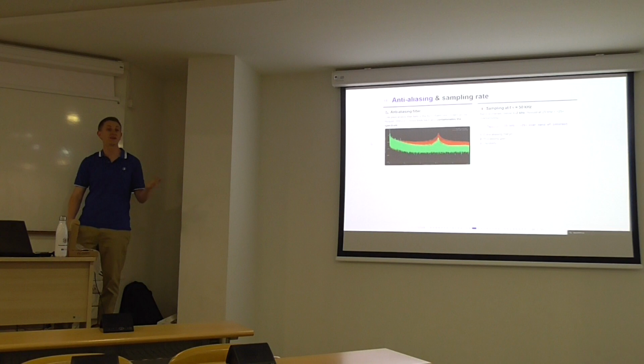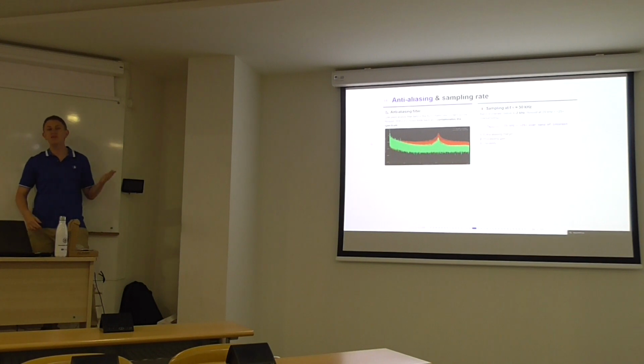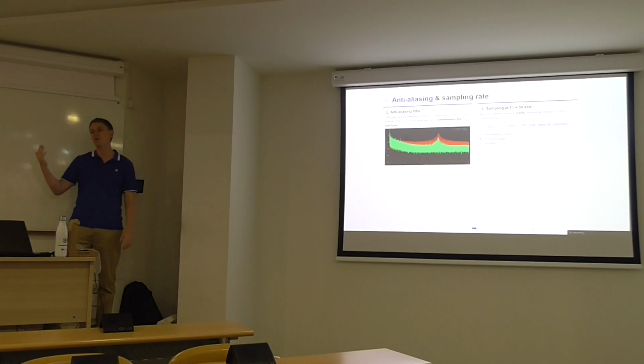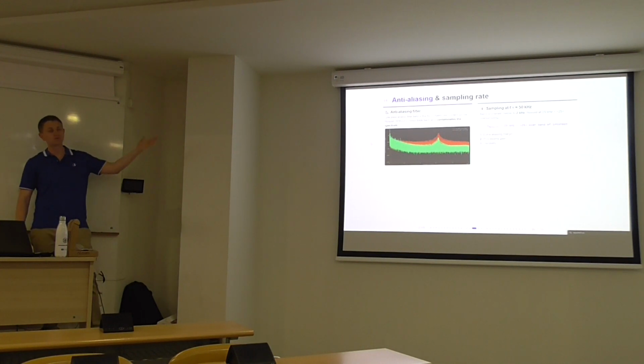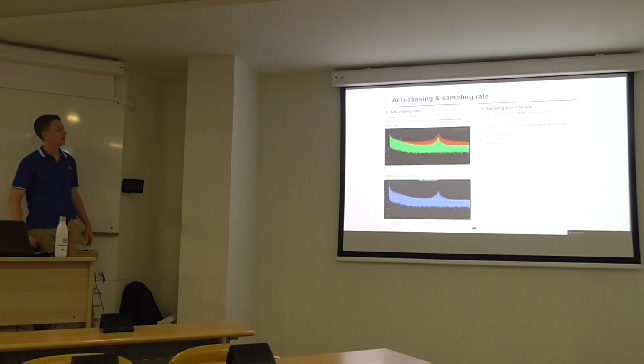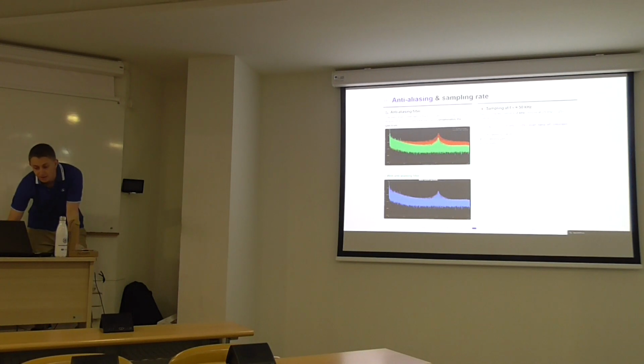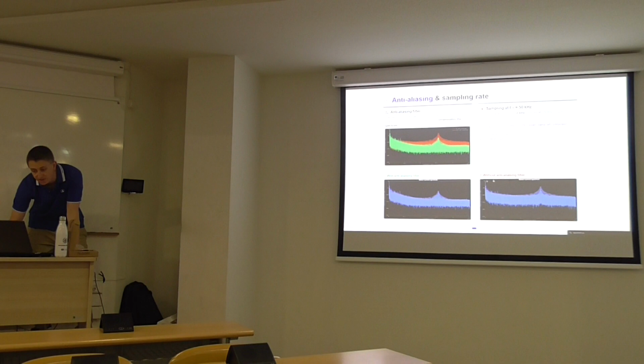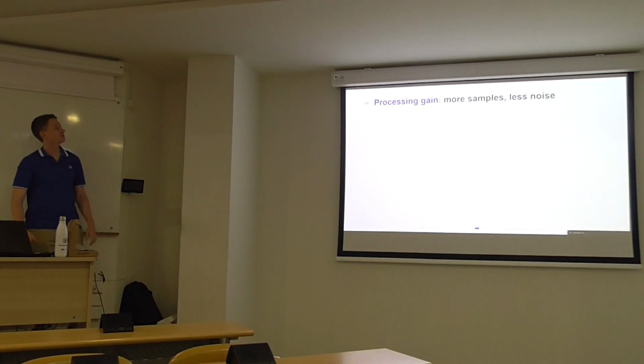And also, it is a matter of flexibility, okay? Maybe now you are only interested in harmonics between 0 and 1 kilohertz. But what if in the future you come up with a new methodology that uses harmonics at 3 kilohertz, 4 kilohertz, and you want to use the signal you have already acquired to check that methodology? Well, if you sample only at 4 or 2 kilohertz, you won't be able to do it. But if you have oversampled, you will always be able to do it. Okay? So my recommendation: always oversample. And here, once again, the spectrum with and without anti-aliasing filter. You can see very clearly how the noise here is much higher than here. Okay? Well, now let's go to the processing gain.